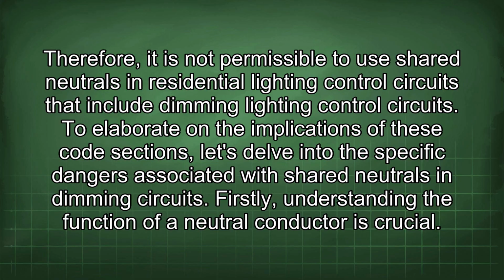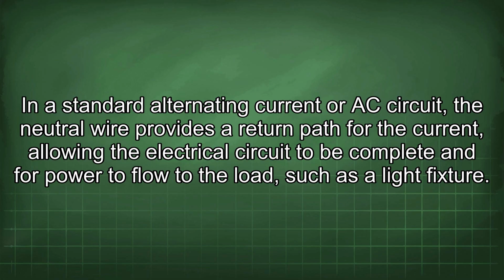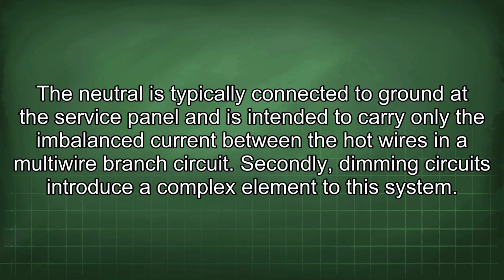To elaborate on the implications of these code sections, let's delve into the specific dangers associated with shared neutrals in dimming circuits. Firstly, understanding the function of a neutral conductor is crucial. In a standard alternating current or AC circuit, the neutral wire provides a return path for the current, allowing the electrical circuit to be complete and for power to flow to the load, such as a light fixture. The neutral is typically connected to ground at the service panel and is intended to carry only the imbalanced current between the hot wires in a multi-wire branch circuit.